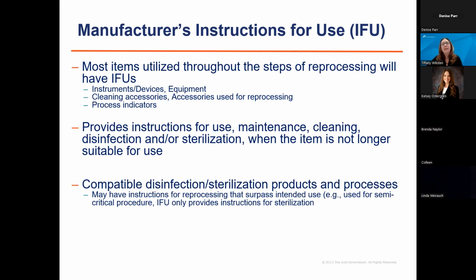I encourage you to take a look at your biologic indicators and make sure that they are compatible with the sterilization cycle that you're validating. Several of these biologic indicators have a whole page of compatible cycles. And I can tell you those surveyors can sniff out the one time where you have a biologic indicator that's being used for a cycle that it's not approved for. The manufacturer's instructions for use provide instructions for use, maintenance, cleaning, disinfection, or sterilization, and when the item is no longer suitable for use, right? And they also will tell you compatible disinfection and sterilization products and processes. So again, they may have instructions for reprocessing that surpass the intended use.